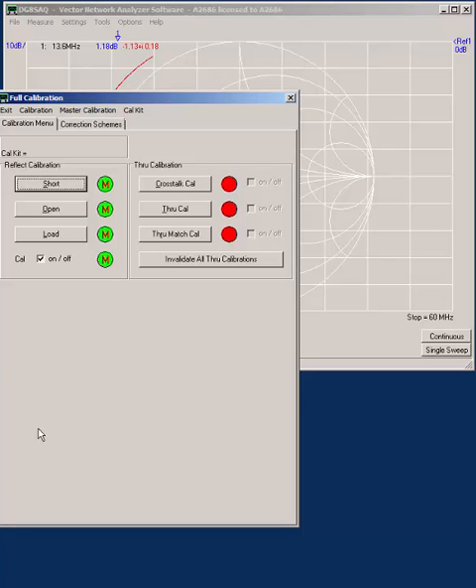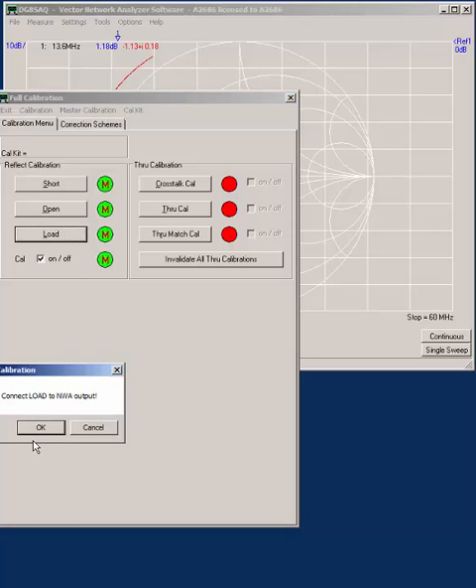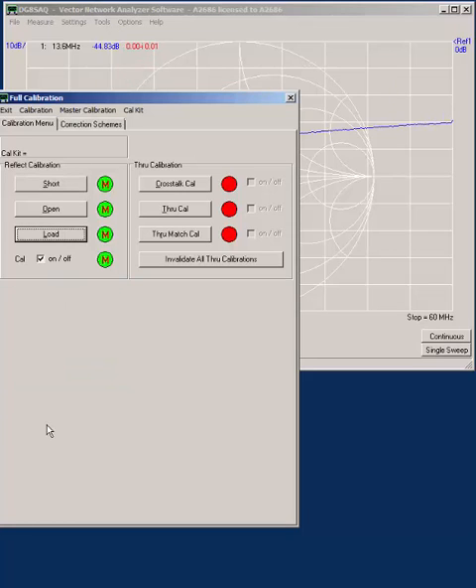The last step in the calibration is to connect the 50 ohm load to the end of the cable. Once that's connected, you click on load and say OK, and now the device is calibrated.